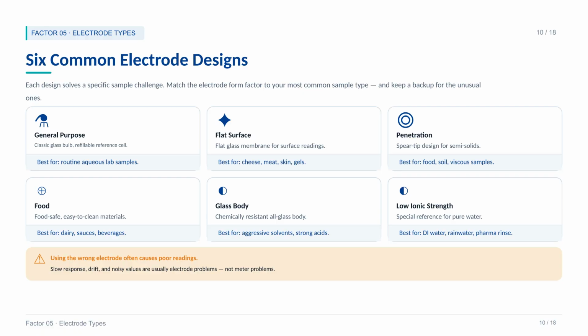Penetration tips for food and soil, food-grade electrodes for dairy and beverages, glass body for aggressive chemicals, and low ionic strength electrodes for pure water. Using the wrong electrode is the single most common cause of slow, drifting, and unreliable readings. So pick carefully and keep a backup for the unusual samples.